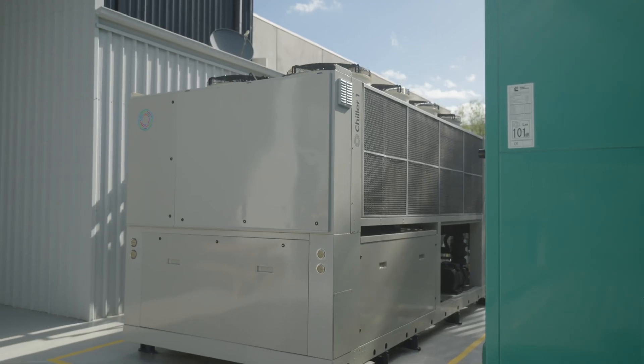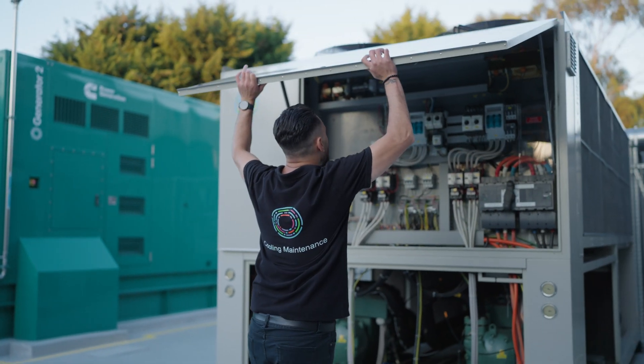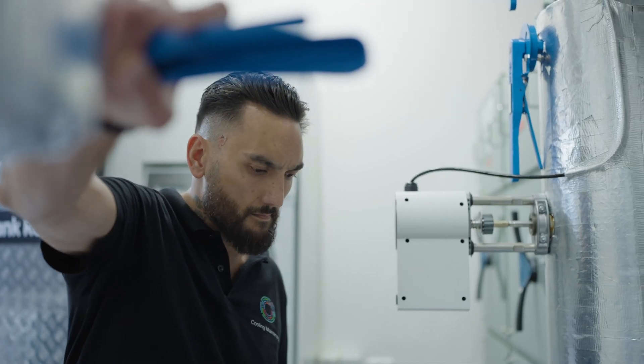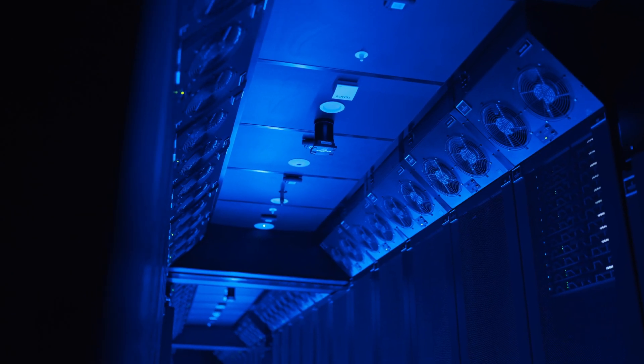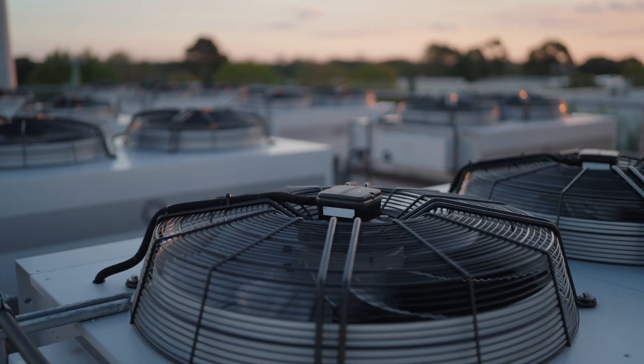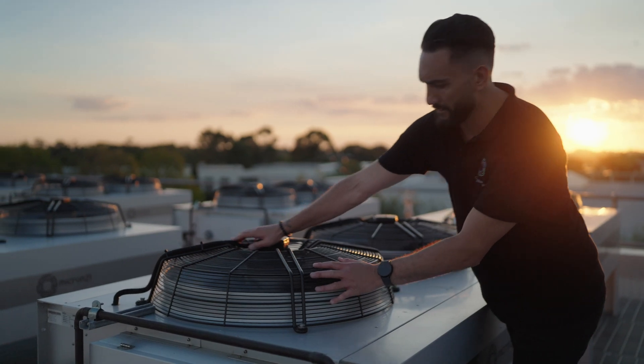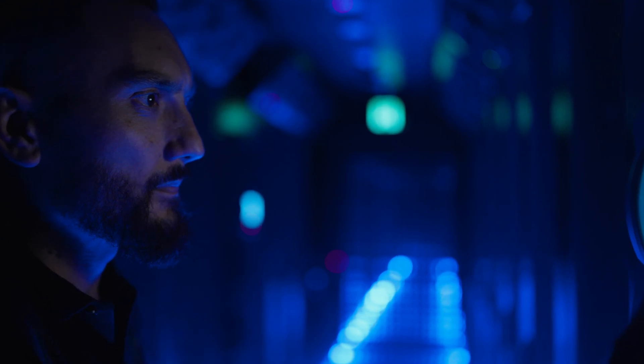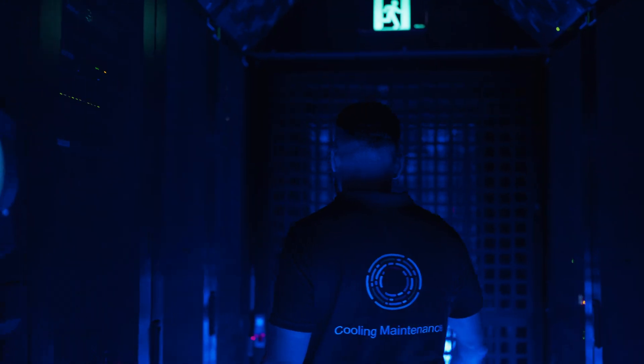Our cooling technology is also based on a 3N design. The primary and secondary cooling technology uses chilled water, including 30,000 litres of thermal storage, allowing for dedicated continuous cooling for each and every rack. In the very unlikely event that both chilled water systems fail, our fully automated tertiary DX refrigeration platform, comprised of 12 independent units, will cool our facility. Collectively, our 3N design allows us to provide continuous and fully automated power and cooling to the data centre, even after multiple technology failures.